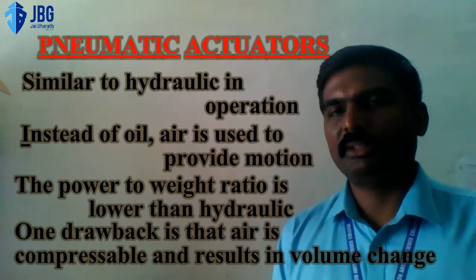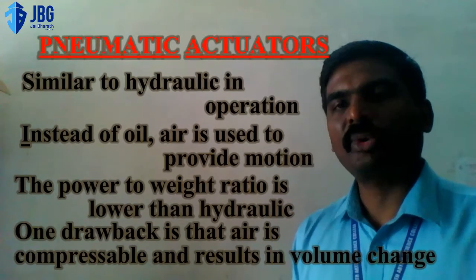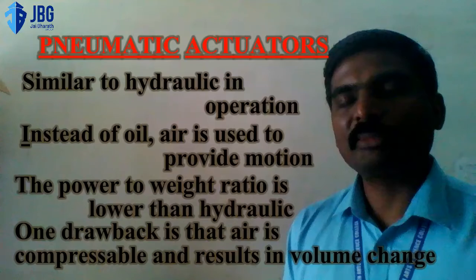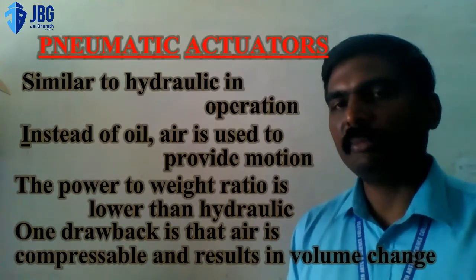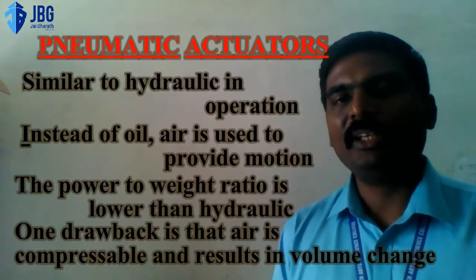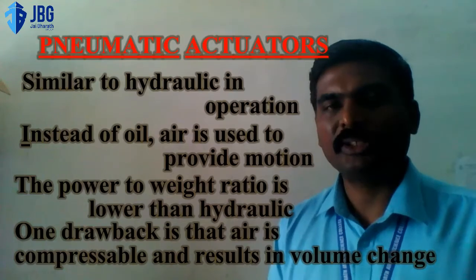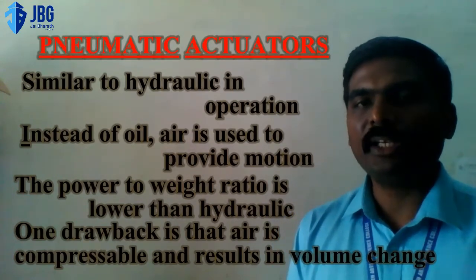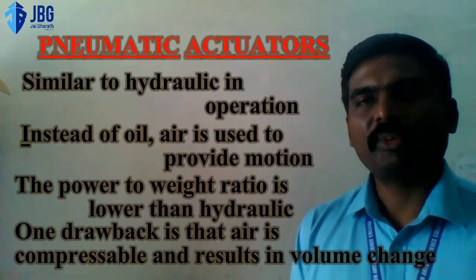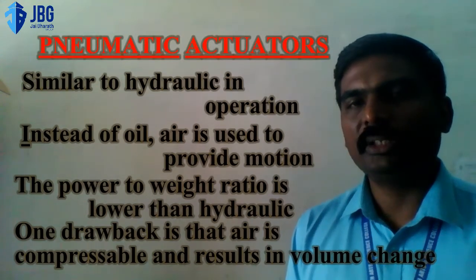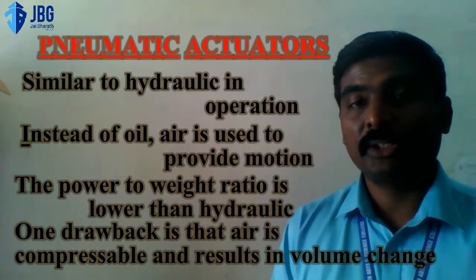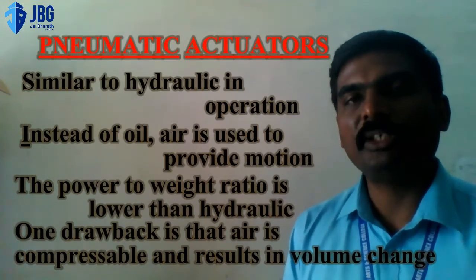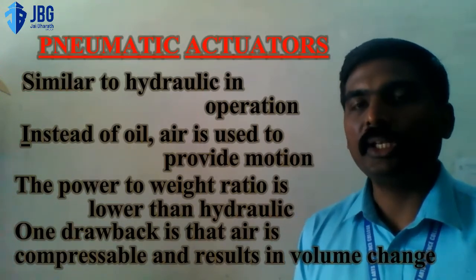The only problem is there is one major drawback with air: air is compressible and therefore the volume can be changed. That's the only problem with the pneumatic actuator. Also, the power to weight ratio is lower than hydraulic, therefore we are not able to use it to handle heavy loads. Those are the differences between pneumatic actuators and a hydraulic system.